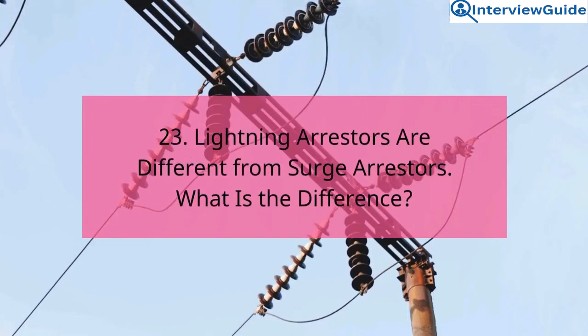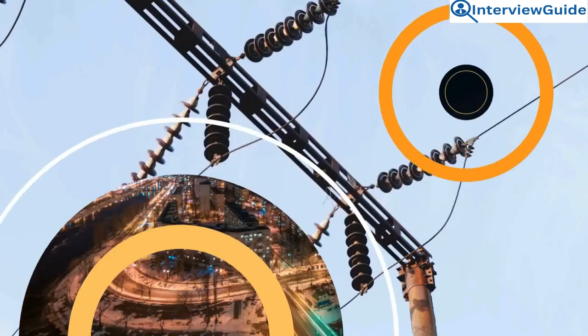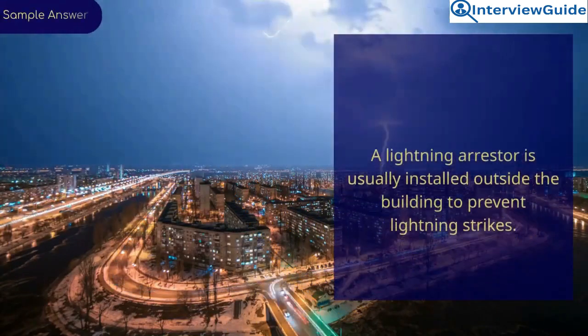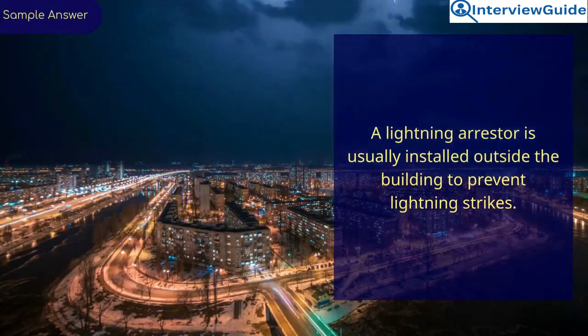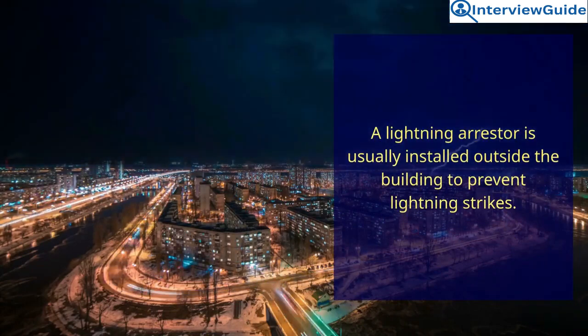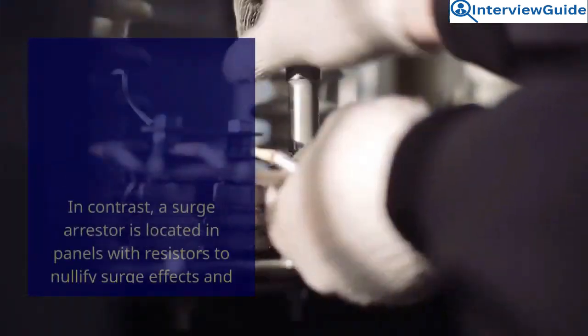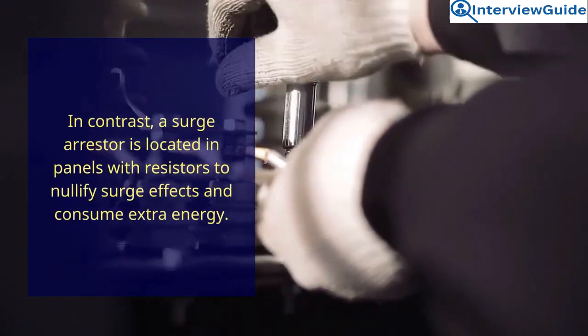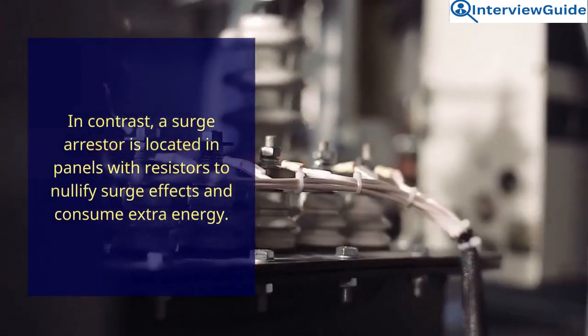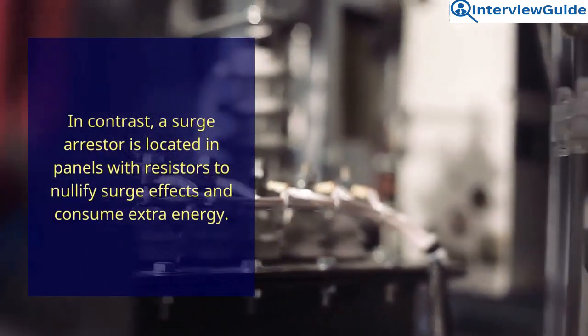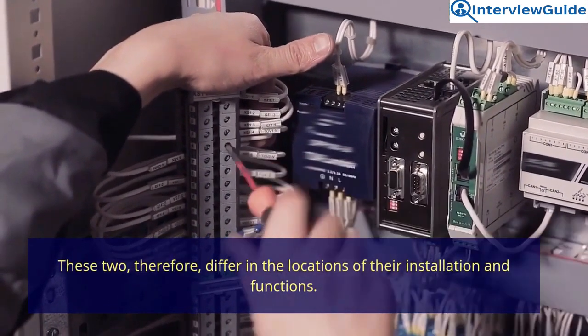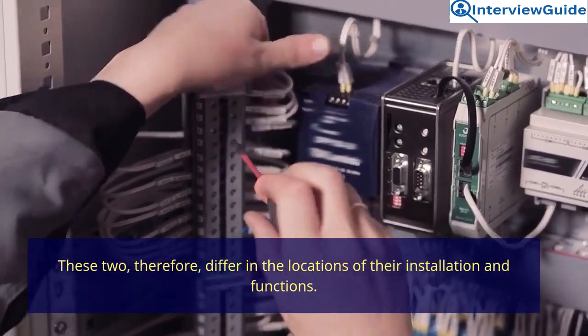23. Lightning arrestors are different from surge arrestors. What is the difference? Sample answer. A lightning arrestor is usually installed outside the building to prevent lightning strikes. In contrast, a surge arrestor is located in panels with resistors to nullify surge effects and consume extra energy. These two, therefore, differ in the locations of their installation and functions.